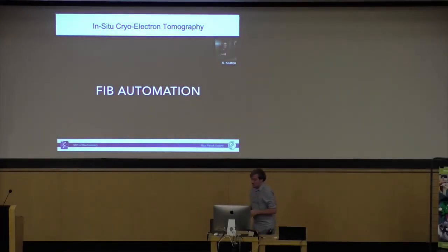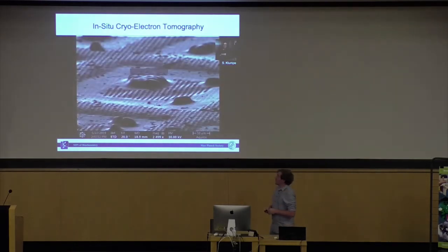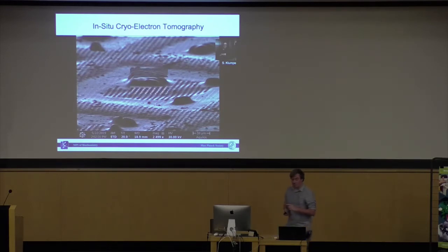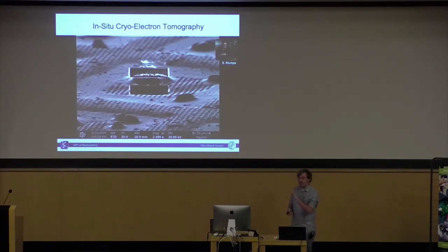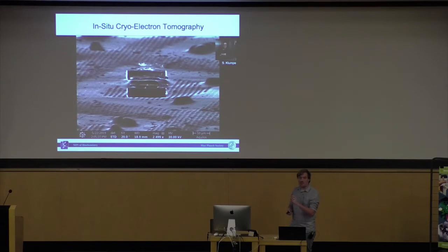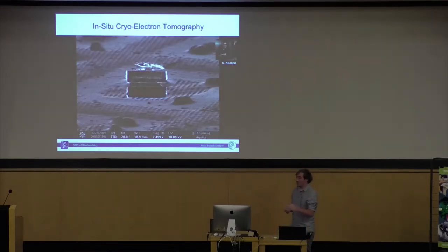What I find works best personally is to let the automation do everything but the very final fine milling, both for our software and Autotem — because I need lamellas at 150 nanometers and below, ideally 140 and below. That final step is still best done manually in my opinion, but hopefully soon we'll have solutions that regularly give you that.